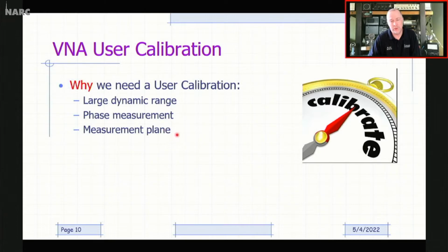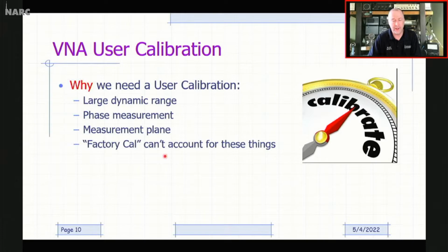And the process of doing that is something called establishing a new measurement plane. So by measuring or doing a calibration effectively at the ports of the DUT, you effectively can remove the effects of all the interconnect that you have going up to the DUT. And of course, no factory cal can account for these things, right? There's no way when they build a VNA that they know what you're going to use to connect from the ports of the DUT to your device. So since you can't account for all of these things, we need to run this user calibration to establish that measurement plane, get rid of the phase and attenuation, et cetera, of the interconnects, and get rid of other systematic errors to give us that large dynamic range.